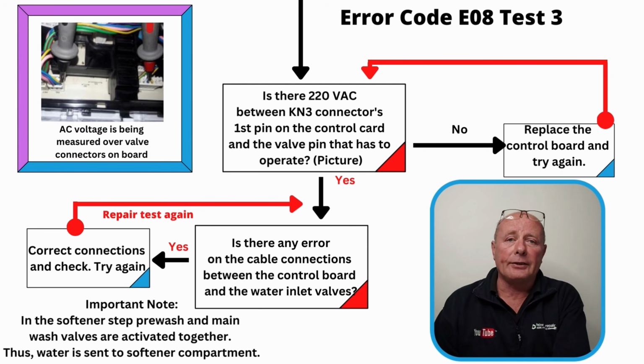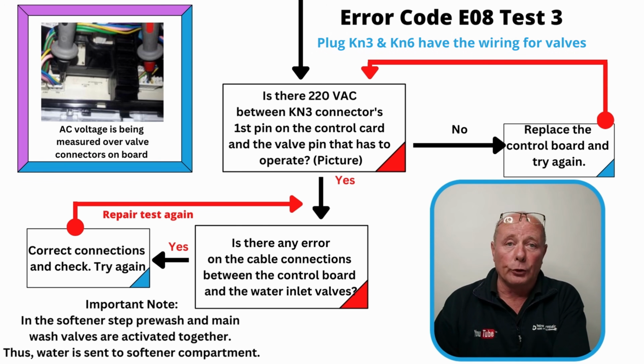If test 1 and test 2 are good, then you may have a problem with the circuit board, and you will need to ascertain whether you have power coming out of the circuit board, and this will vary from model to model. The instructions I'm putting on this repair guide on the website are to do with the WTK range of machines.